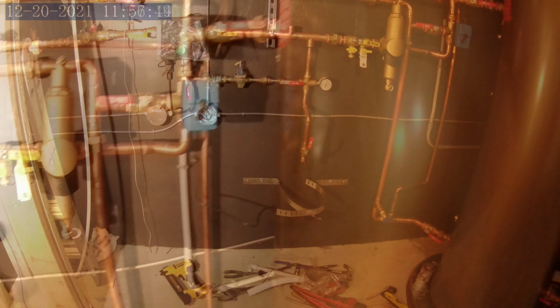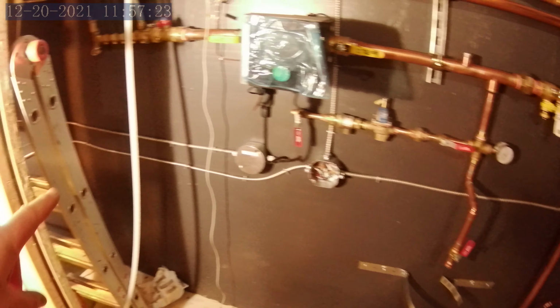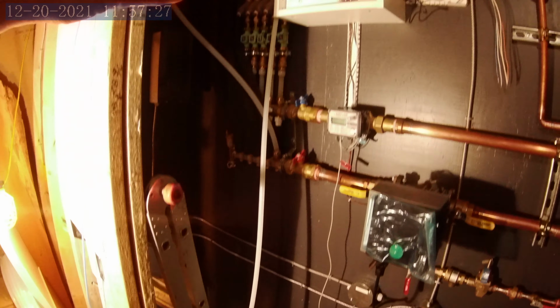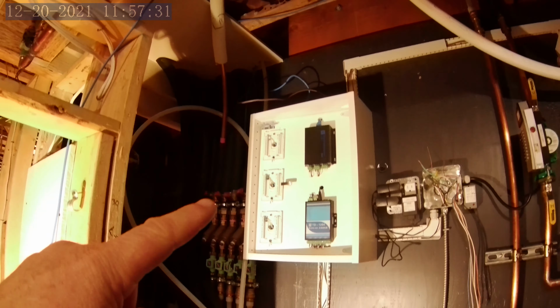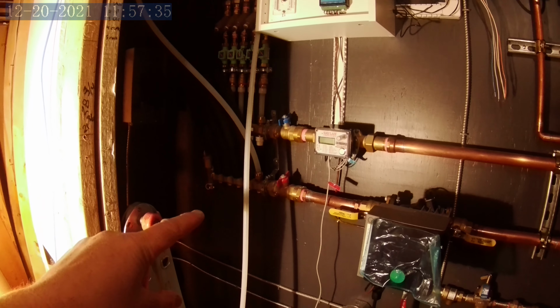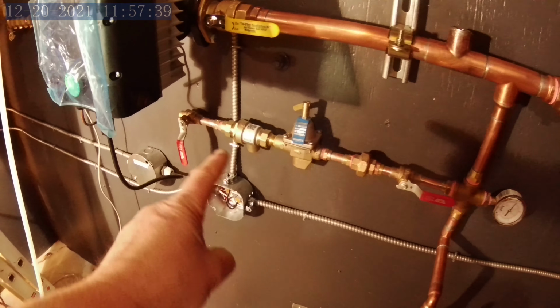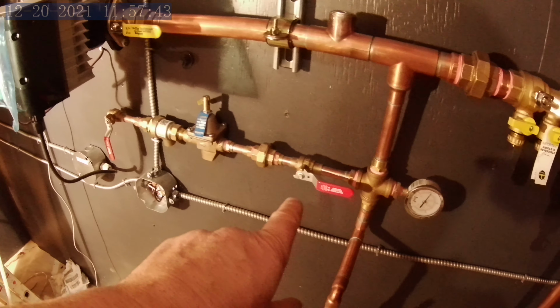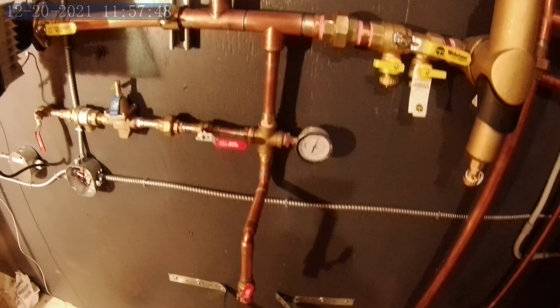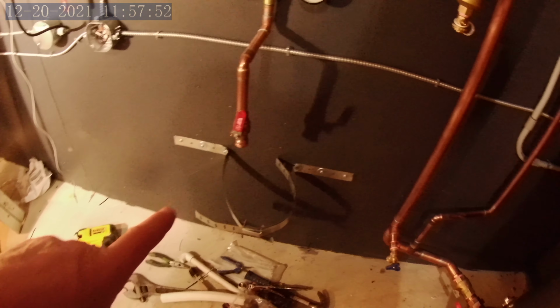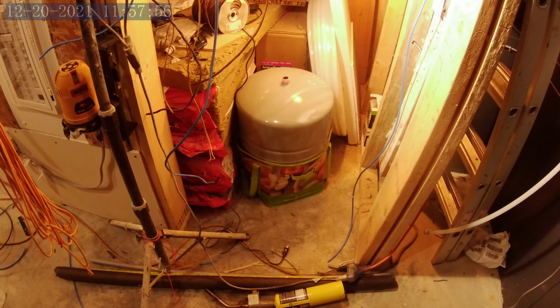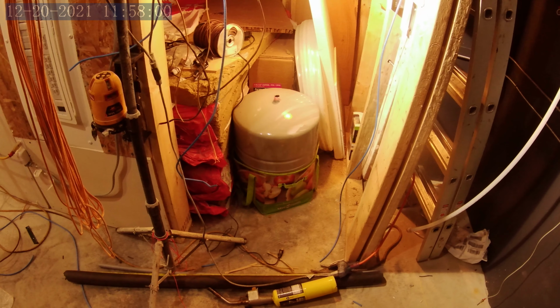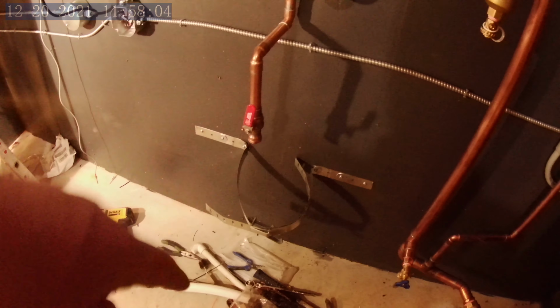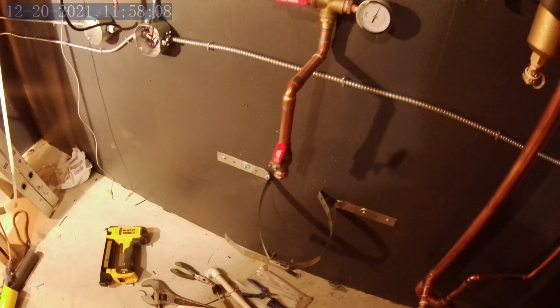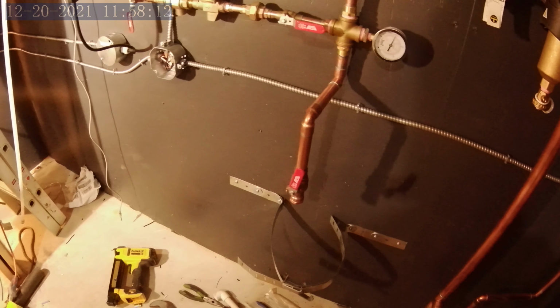Okay, I will now just give you a quick look outside, and then we are done. Just forgot to talk a little bit about the feed station. So this PEX line is the feed to the system. I'm going to convert it over there to copper and bring it down so I can bend the copper around here and then over to the feed. And we've got a backflow preventer, we've got a pressure reducer, and then a shutoff gauge so we can tell what the pressure is in the system. And then this will be where the expansion tank goes, which is right over there. And I just have it out of the way. I don't want to have it installed while I purge the system. I don't want to get any gunk in there. I'll be able to use this to dump the air and the debris out of the system, as well as these purge valves. But that's where it'll end up eventually.